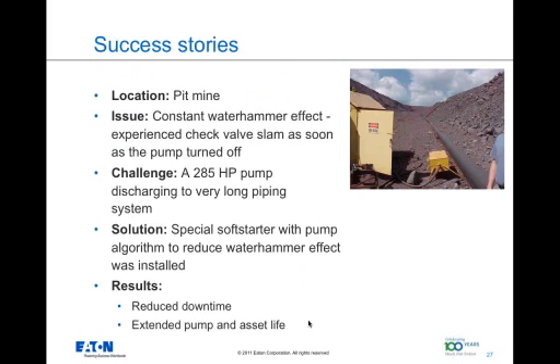We have had numerous success stories with usage of soft starters and conversion of customers from traditional ways to soft starters, but this is one example I wanted to present. We had a pit mine customer, and they were troubled with the constant water hammer effect. They experienced check valve slamming continuously as soon as the pump turned off. They had extended amounts of downtime because of the maintenance which went into fixing the check valves at the end of the pump cycles.